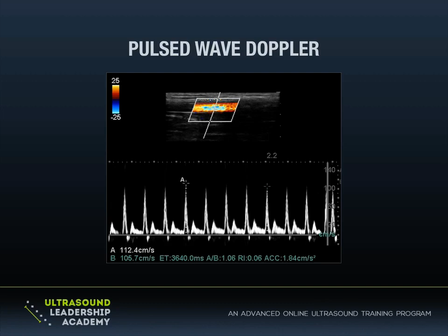This is aliasing. This is what happens with pulse wave Doppler when it can't handle the high velocities that you're seeing. And it gets confused as the velocity of the Doppler shift exceeds the Nyquist limit, which is the speed at which aliasing happens to the signal. And here's the baseline. And you've got the systole here, and then diastole, and systole and into diastole. But at systole, you're starting to see the peak of systole show up as a negative amplitude and as a negative Doppler shift. And that's aliasing or wraparound. And that's just a function of pulse wave Doppler being unable to handle these high velocities.